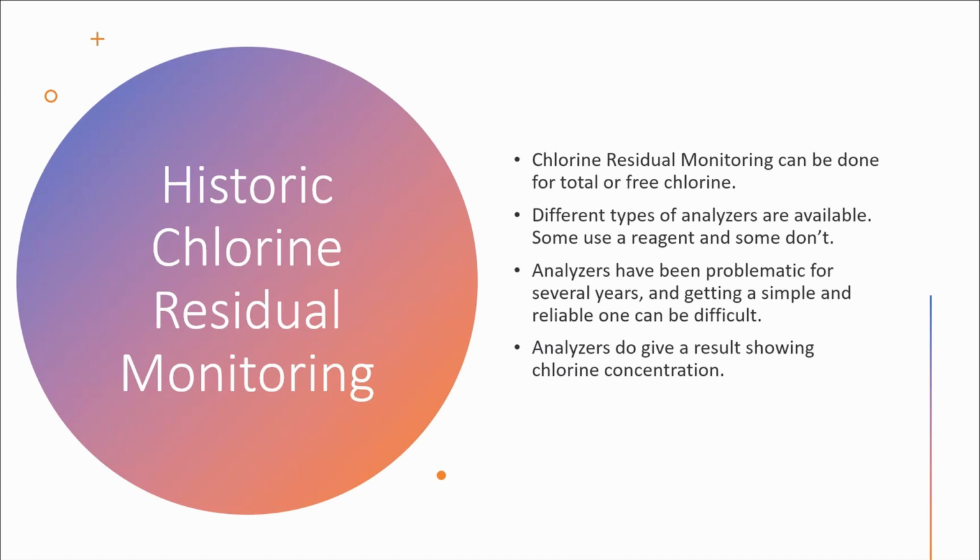There are different types of analyzers that are available. Some of those analyzers require a chemical reagent, and some of those don't. They have been problematic for many years. I can just remember the first project I was on in the early 90s, a treatment plant in central Utah, and the lead operator was just cussing, trying to recalibrate his chlorine residual analyzers. They were pacing their disinfection with their contact chamber and just could not. They thought they'd have it all set up and they'd walk away and leave it alone and come back the next day and things were off, or come back the next week.